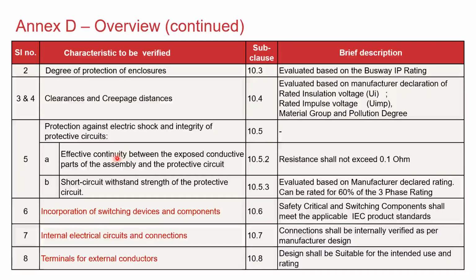We basically have two tests. One is to find out the effective continuity. There the resistance shall not exceed 0.1 ohms. Then we also have another test wherein we need to do a short circuit withstand test or withstand strength test of the protective circuit, depending on what the manufacturer declares for.